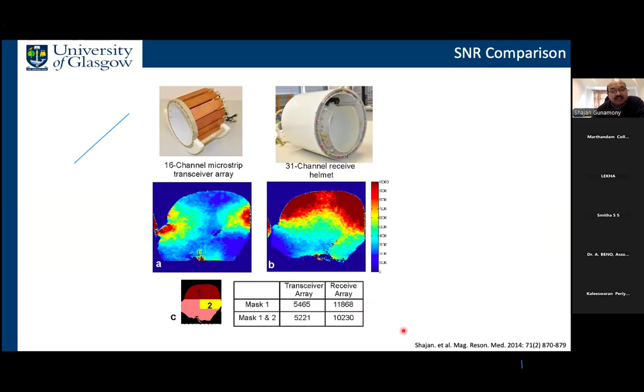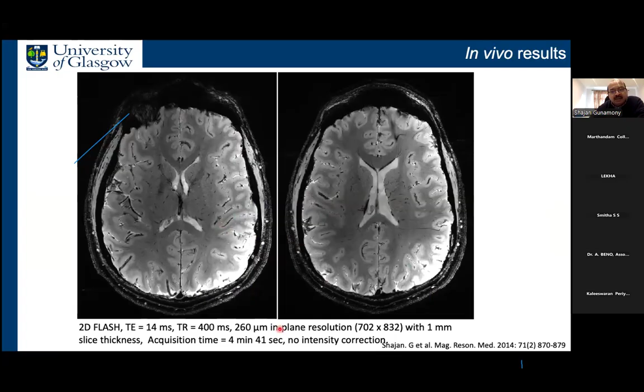Okay, so now you see the comparison of these two coils, and the first one is the microstrip array, and then the new coil, because this now has 16 transmit and 31 receive. You get so much more SNR with this new coil. In both these regions here in mask 1 and 2, you see the SNR gain is more than a factor of 2. So these are some in vivo images that were acquired with this coil, with a resolution of about 260 micron. This was acquired in less than 5 minutes.